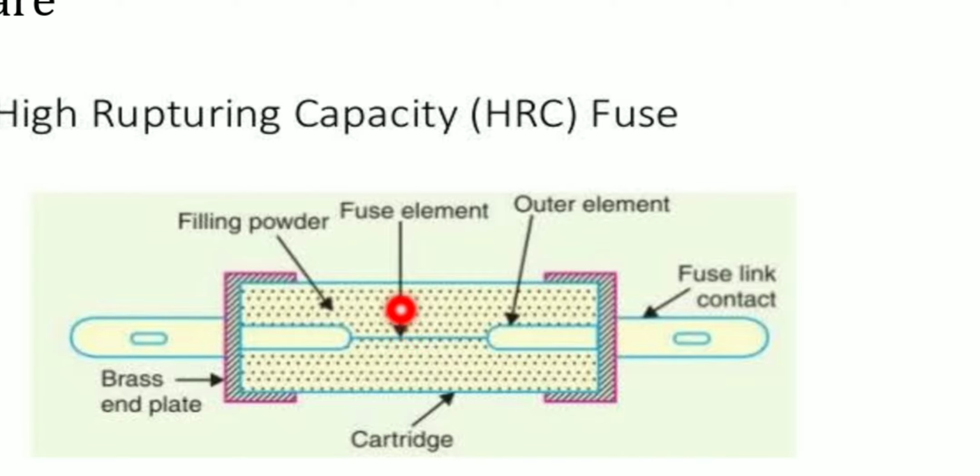So then what will happen? Inside, the filling powder will be there, that is quartz or something else. This filling powder is of such a quantity that a chemical reaction takes place between the silver vapor, nothing but the fuse element that has vaporized, and this filling powder. Both together form what? A high electrical resistance substance. Electrical resistance means opposition to the current. So obviously this substance will quench the arc completely, nothing but it will suppress the spark completely.